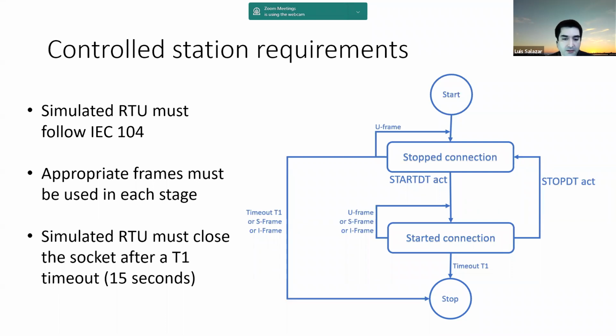During this time, you can send U frames, which are U format packets that will control the connection itself. You can send what is known as the start data transfer command, which will shift the RTU from the stop connection state to the start connection state. And when you receive that, the RTU will start reporting all the measurements to the SCADA, and the SCADA can issue commands to this RTU. This is all part of the IEC 104. And once you are in this new start connection state, if you send a stop data transfer packet, then you go back again to the stop connection state, and you can remain with that same connection, or you can just close the connection with a timeout. Either way, that's the expected behavior of an RTU.